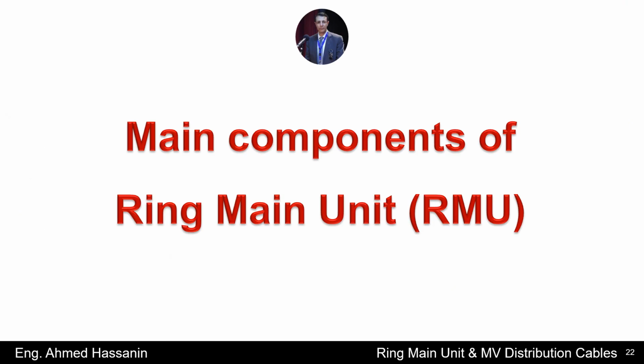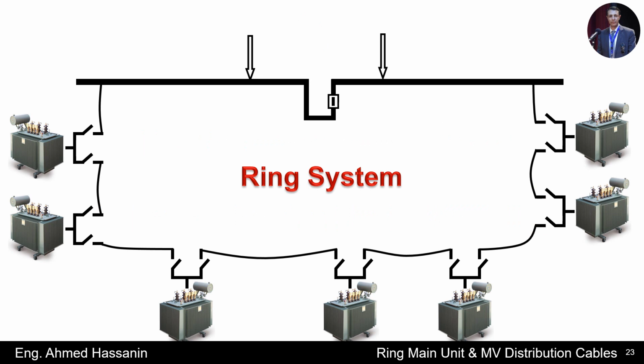I will talk about the main components of the ring main unit. I will talk about the place and the main function of the ring main unit in the medium voltage distribution system. We must know that the ring main unit is the most important part of the medium voltage distribution system, and without this part, we cannot make a ring distribution system or make a connection between the distribution transformers.